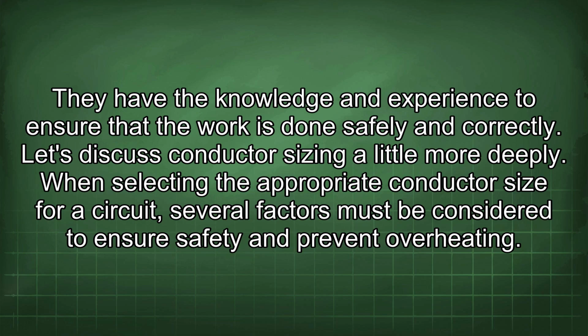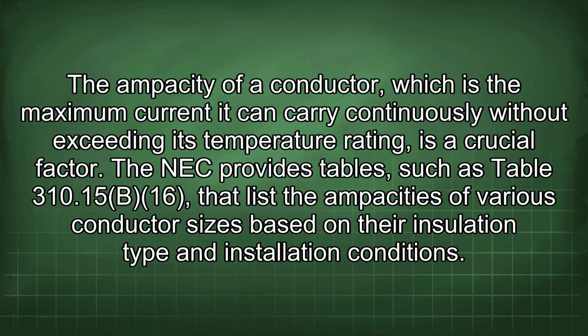When selecting the appropriate conductor size for a circuit, several factors must be considered to ensure safety and prevent overheating. The ampacity of a conductor, which is the maximum current it can carry continuously without exceeding its temperature rating, is a crucial factor. The NEC provides tables, such as Table 310.15(B)(16), that list the ampacities of various conductor sizes based on their insulation type and installation conditions.